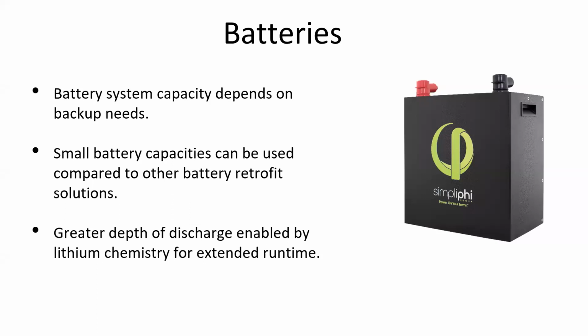Looking at the lithium battery as a whole, why does it make sense to go with lithium for a backup system, specifically LFP, lithium iron phosphate? The good news is with the lithium iron phosphate chemistry, we can have a greater depth of discharge while not giving away too much cycle life. We maintain longevity in the battery while also being able to discharge greatly, which in a backup situation can be helpful to use up to 100% of the battery's capacity if needed.